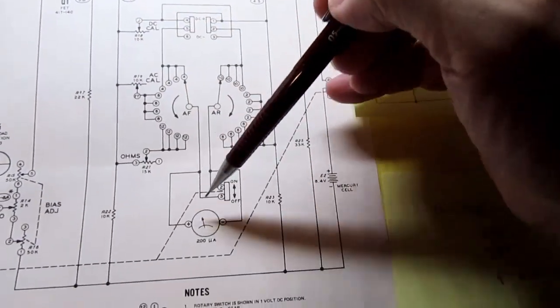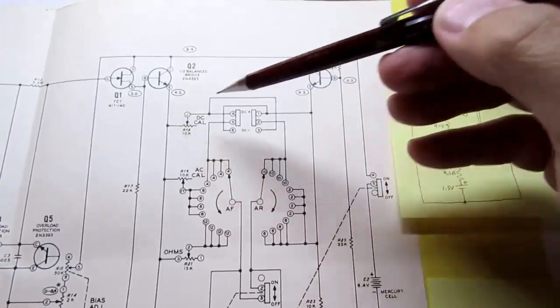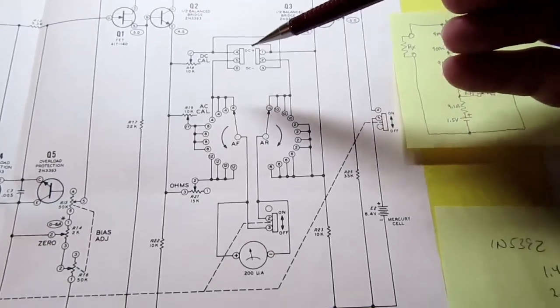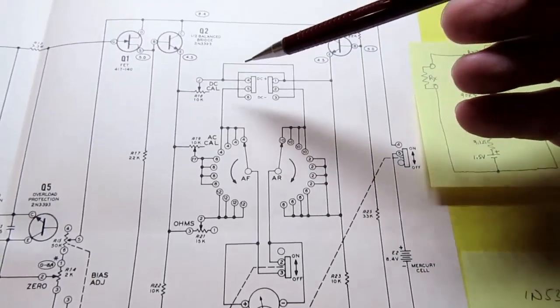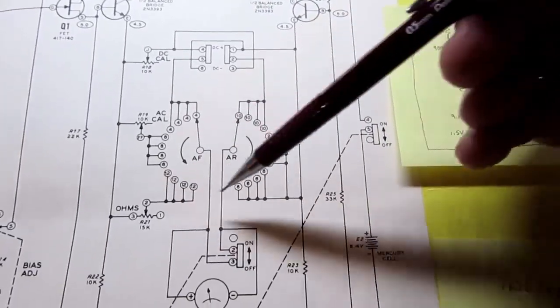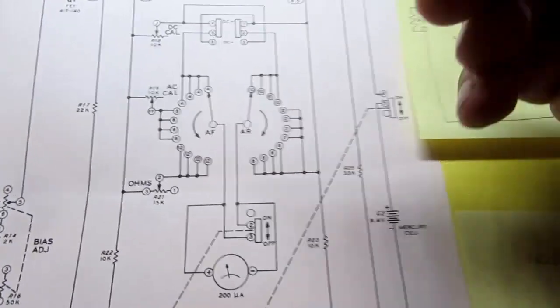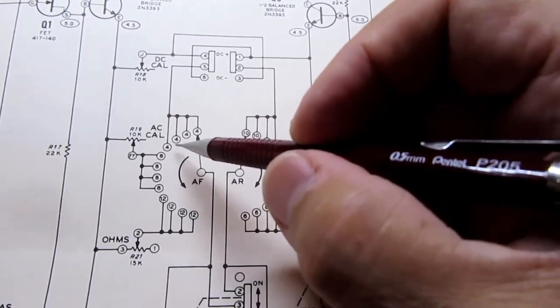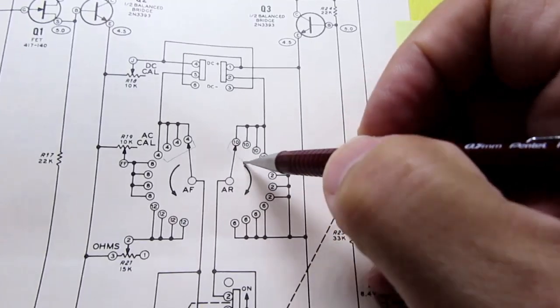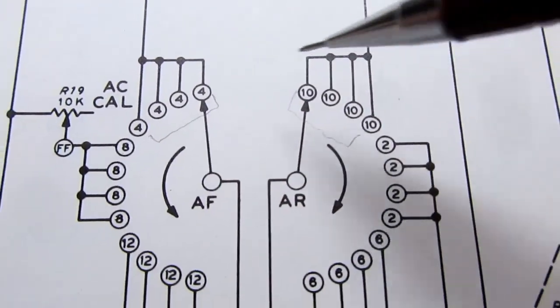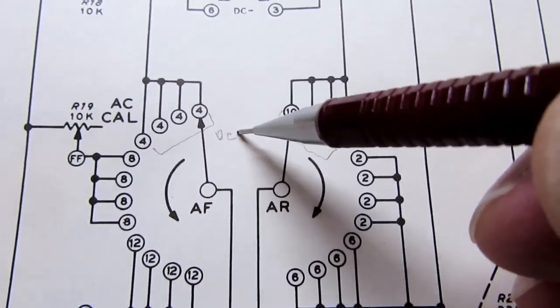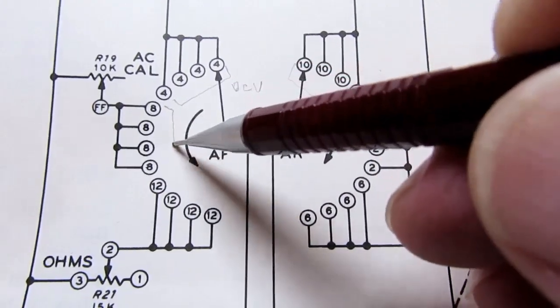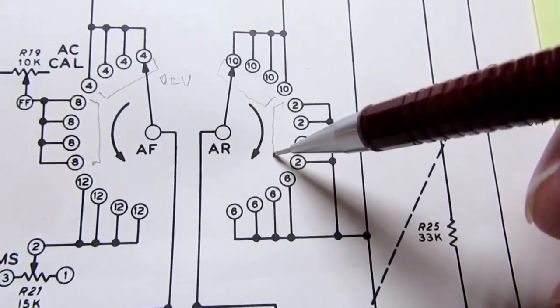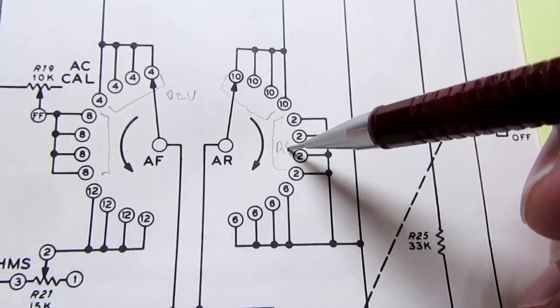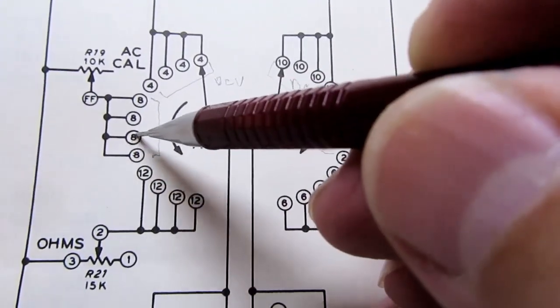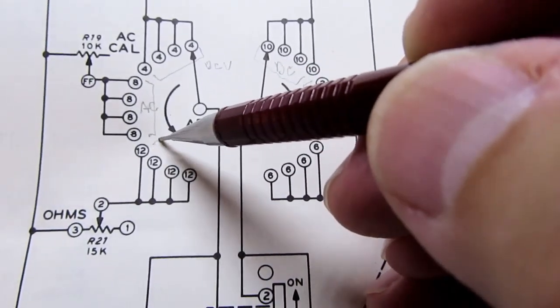Now, how does the meter actually get current to it or through it when you have an imbalance from this side of the meter driver to this side? Well, if you're in a DC range, and again this is the function selector switch here, and it's shown in the 1 volt DC range, so these 4 here and these 4 here are DC volts, and then the next 4, and also these 4, is AC. And then finally the bottom is ohms.